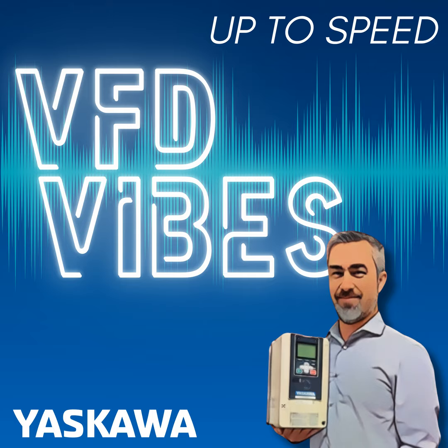Fan checks. Make sure that airflow matches design specs. And many drives have sensors that trigger a warning if a fan slows or fails. Make sure to check your drive for these warnings, or again, if your drive is networked up to a PLC or supervisory system, it's a great data point to monitor so that your SCADA system or an HMI can tell you when you might have a fan failure on your VFD.